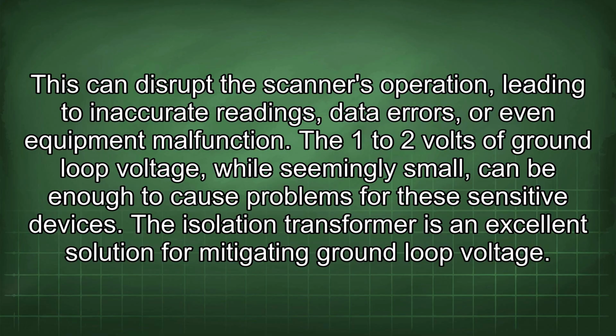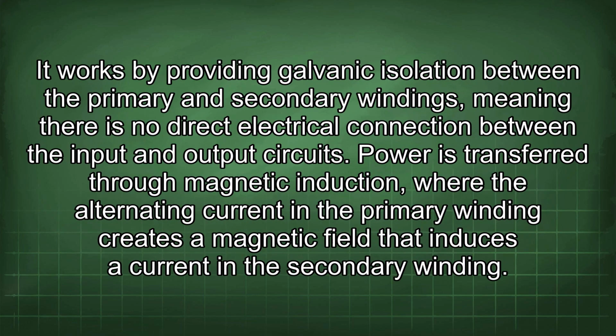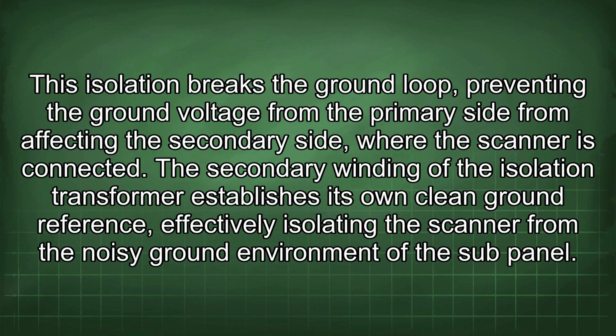The isolation transformer is an excellent solution for mitigating ground loop voltage. It works by providing galvanic isolation between the primary and secondary windings, meaning there is no direct electrical connection between the input and output circuits. Power is transferred through magnetic induction, where the alternating current in the primary winding creates a magnetic field that induces a current in the secondary winding. This isolation breaks the ground loop, preventing the ground voltage from the primary side from affecting the secondary side, where the scanner is connected. The secondary winding of the isolation transformer establishes its own clean ground reference, effectively isolating the scanner from the noisy ground environment of the subpanel.